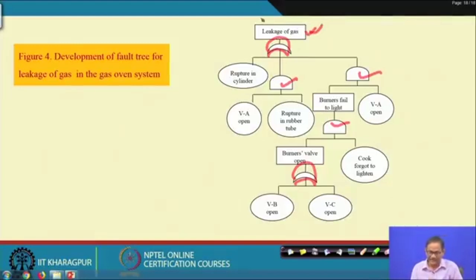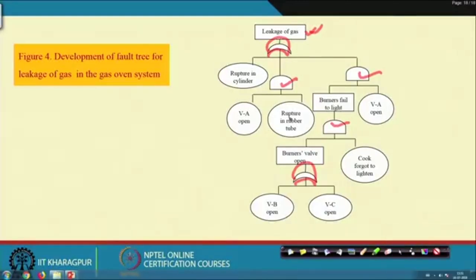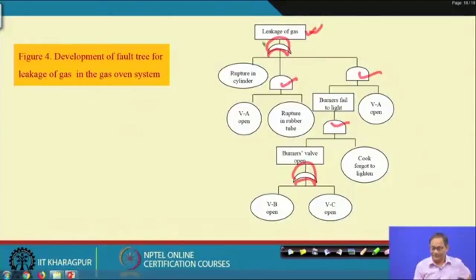because ultimately in safety studies, the top event is the undesired event. Where there are more AND gates, it basically prohibits the undesired event from occurring, and this reduces the probability of the event. So, by constructing a fault tree of a top event, you can find out what the system level vulnerability is. When there are more AND gates, as we are talking about the undesired event, it is a better system configuration. If there are more OR gates or all OR gates, then it is a problematic one.